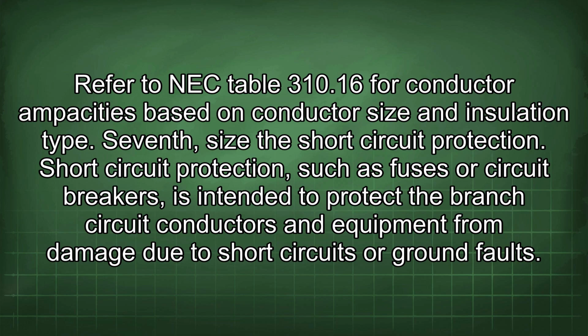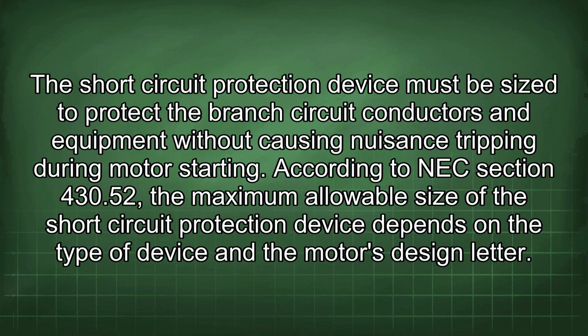Seventh, size the short circuit protection. Short circuit protection, such as fuses or circuit breakers, is intended to protect the branch circuit conductors and equipment from damage due to short circuits or ground faults. The short circuit protection device must be sized to protect the branch circuit conductors and equipment without causing nuisance tripping during motor starting. According to NEC section 430.52, the maximum allowable size of the short circuit protection device depends on the type of device and the motor's design letter.